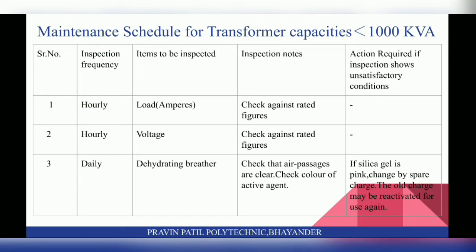For daily basis, you have to check the dehydrating breather. Inspection note: Check that air passages are clear and check the colour of the active agent, that is silica gel. If silica gel is pink, change it with a spare charge — the old charge may be reactivated for use again.